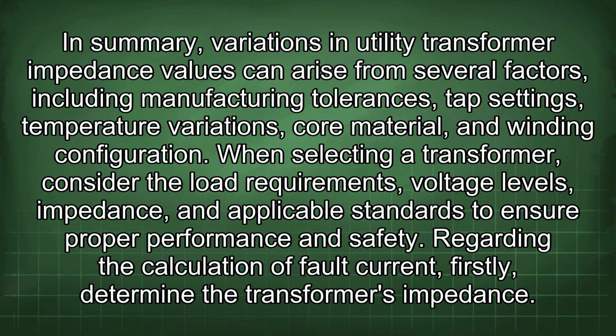In summary, variations in utility transformer impedance values can arise from several factors, including manufacturing tolerances, tap settings, temperature variations, core material, and winding configuration. When selecting a transformer, consider the load requirements, voltage levels, impedance, and applicable standards to ensure proper performance and safety.